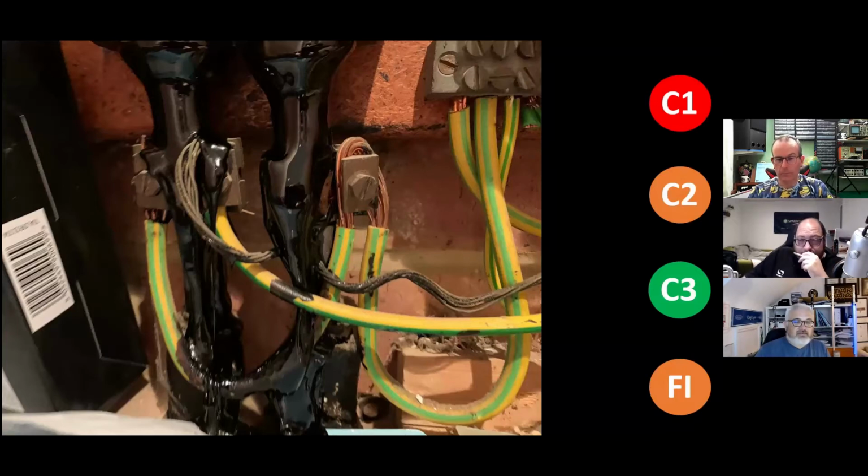We're lucky we've got some amazing pictures of some pitch leakage, because it is a phenomenon where you really do have to start looking at a lot of things and getting the DNO involved. Because as you know, Dave, we've recently found a loose connection inside of a DNO head. I've found a number of loose connections on fuses and stuff using thermography as a tool. Even on the Flir One Pro, do you remember I plugged it in and found it very quickly on a main fuse intake?